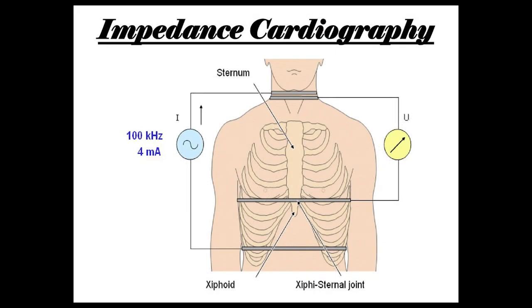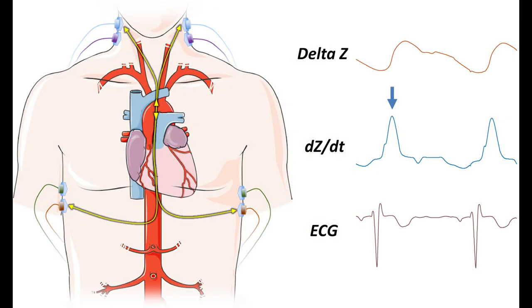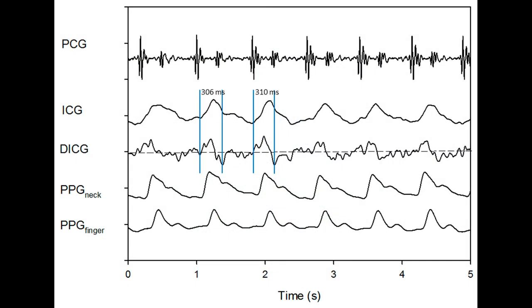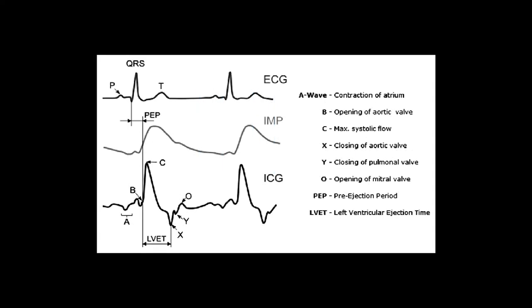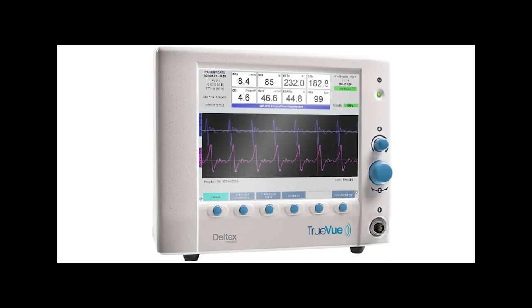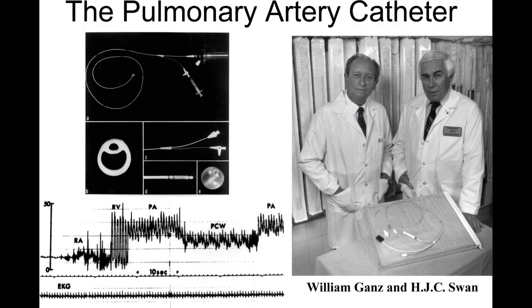The next method is impedance cardiography, which has been in development since the 1960s. This is a non-invasive method that uses electrodes positioned around the thorax to measure electrical conductivity of the thorax. As blood is pumped through the heart and aorta, it changes the impedance between the electrodes and creates an electrical waveform. These waveforms are used to calculate a variety of hemodynamic parameters. The major advantages are its non-invasive technique and the ability for long-term continuous monitoring — many companies are still developing this technology.